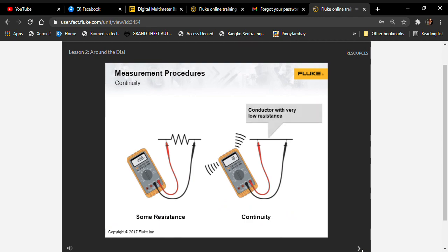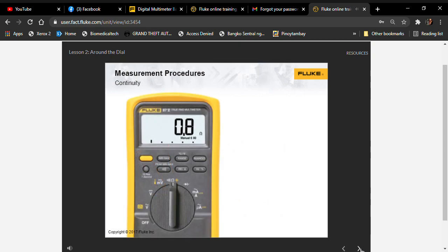Continuity is the condition of having a very low resistance connection. The only difference between measuring resistance and testing continuity is that a multimeter with an audible function will beep if resistance is considered low enough for continuity. The beep is helpful because it allows you to conduct continuity tests quickly without the need to view the display. Multimeter manufacturers may each define the resistance level that triggers continuity differently. But for our multimeter, a resistance less than about 30 ohms triggers the beeper for continuity if the audible feature is selected. Your meter may default to beeping for continuity, or you may have to press a button to turn the feature on. A continuity symbol looks like a series of sound waves.